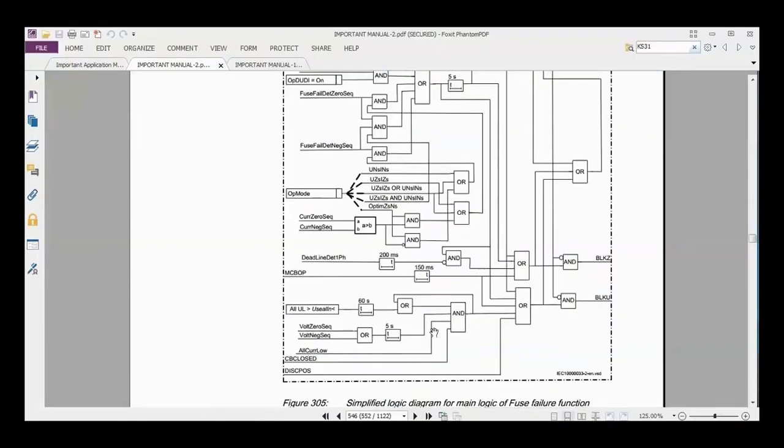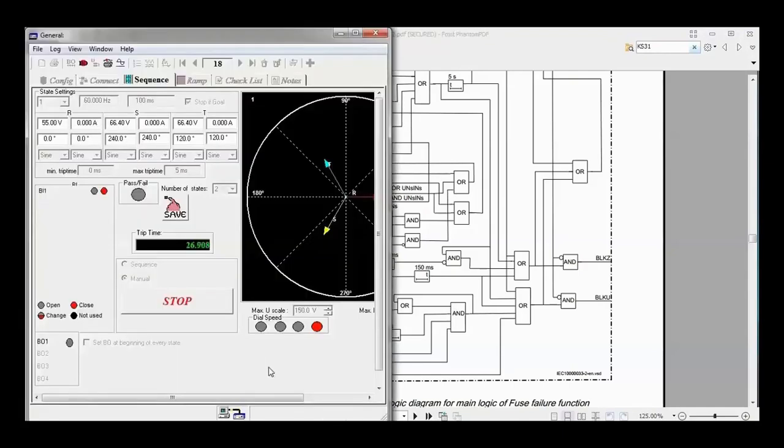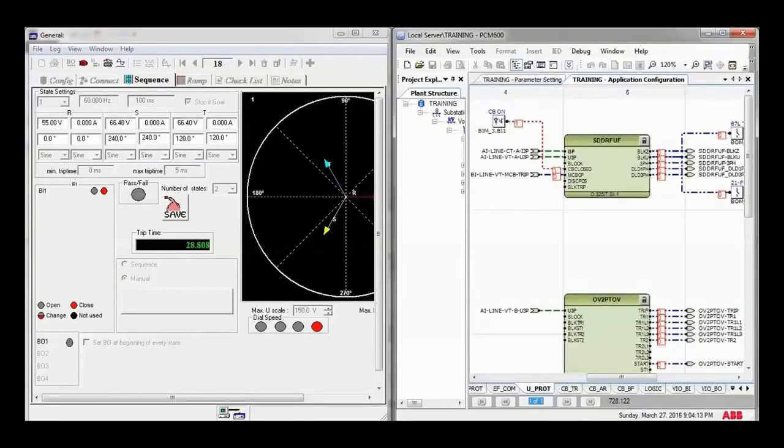There is no current low, no breaker close, and all voltages are greater than UC, which is 70% of the 66 volts, which is 46 and a bit. And at that time, some had a phase fail, so those 5 seconds actually passed while those 60 were passing. Those 5 seconds actually passed and a 1 came out here. So as soon as the 60 finishes, it gives you a 1 here, and a block comes out immediately. So we will see the initial test, and then we will see the other cases and how they address them again.